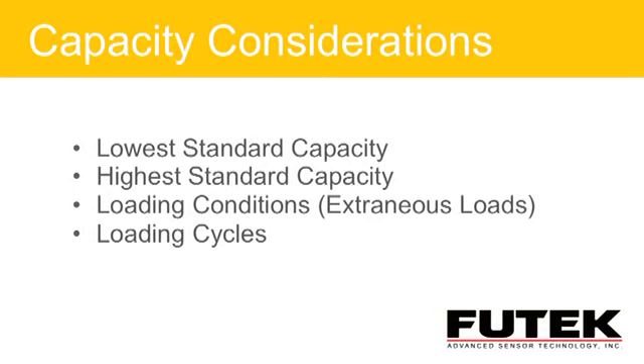How low a capacity do you need? FUTEK has currently provided solutions in the full scale range of 10 grams, yet can measure down to 1 milligram resolution and 3 milligrams accuracy. On the highest standard ranges, FUTEK has done up to 1 million pounds. That's not the limit. You can keep pushing the limits higher if necessary. That's, of course, where the budget comes in.